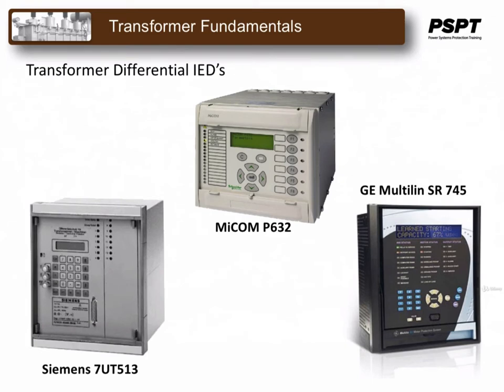Compensation for the transformer primary tap changer is also accounted for when applying relay set points. Harmonic restraint is provided and addresses the problem of false tripping for magnetizing inrush current during transformer energization. The relay settings are entered using application software run from a computer, usually a laptop, that's brought into the field.